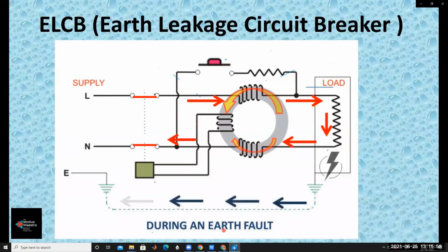Flux is developed in the CBCT, in the core of the transformer, so this sensing coil will sense it. For example, 2 Weber of flux is induced because of this coil, but here only 1 Weber. So 2 minus 1, 1 Weber of flux is induced in the sensing coil, and then the sensing coil trips the circuit and opens the contact. Like this, this ELCB is working under earth fault condition.